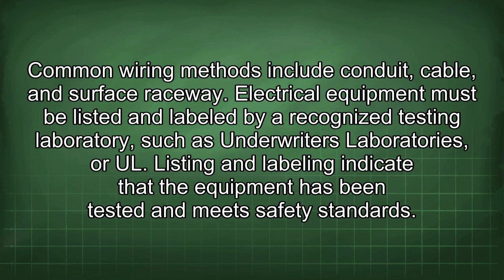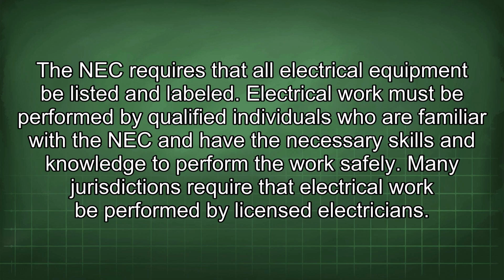Electrical equipment must be listed and labeled by a recognized testing laboratory, such as Underwriters Laboratories, or UL. Listing and labeling indicate that the equipment has been tested and meets safety standards. The NEC requires that all electrical equipment be listed and labeled.